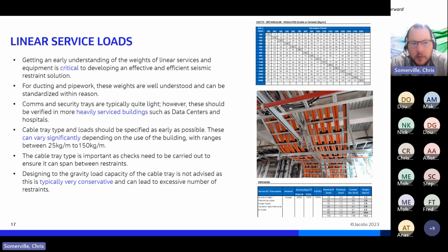The key with the cable trays is we like to know what cable ladders you want to use, the type, because we have to check that they can actually span the distance between restraints. We need to understand that the cable ladder can bend horizontally in its weak, out-of-plane direction between two points. So we need to know what cable trays and ladders you want to use so we can do those checks early on, and that may set the positions of some of our restraints as well. It's something we have to consider.